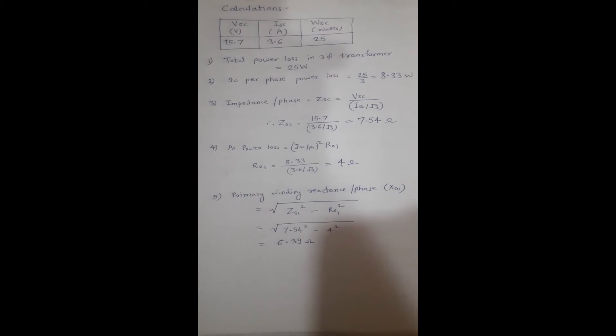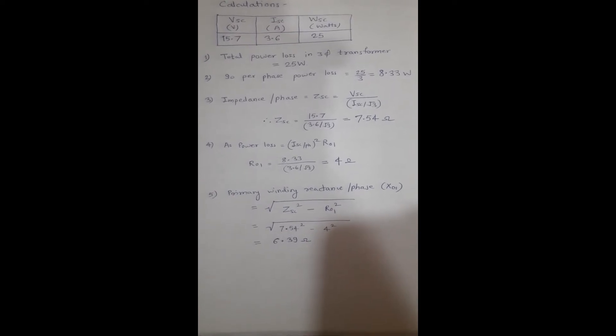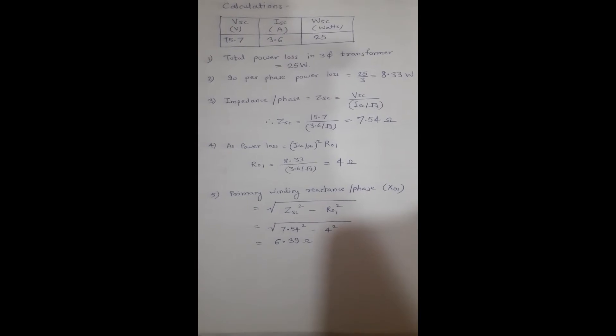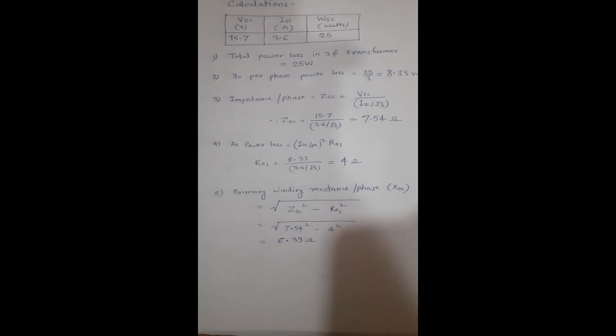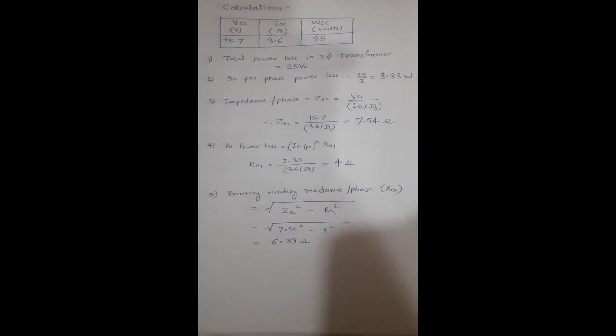With all readings in the observation table, we can find the different parameters. Total power loss in the three-phase transformer is 25 watts, so per phase power loss is 25 ÷ 3 = 8.33 watts. Since the primary winding is in delta, we calculate the per phase current accordingly. For Zsc we use the formula Vsc ÷ (Isc ÷ √3), giving Zsc = 7.54 ohms.